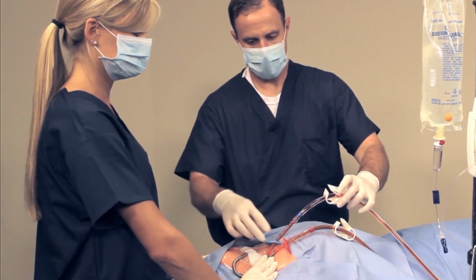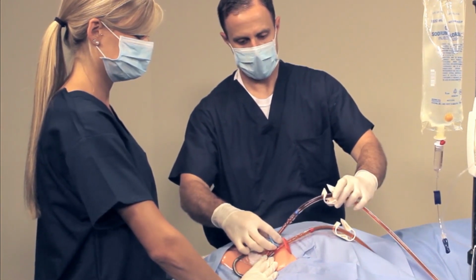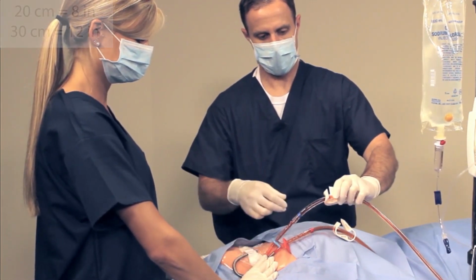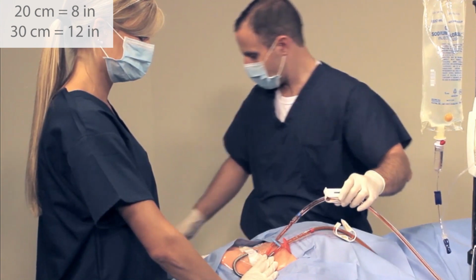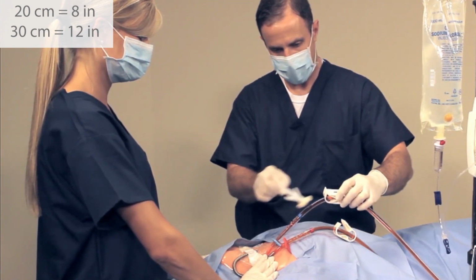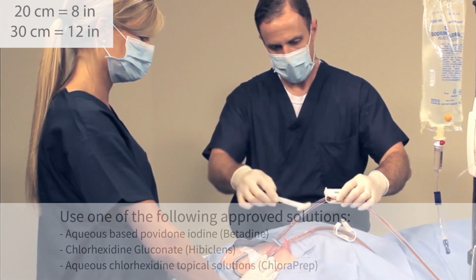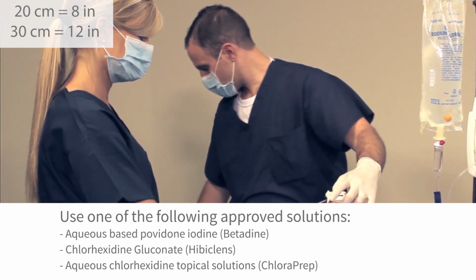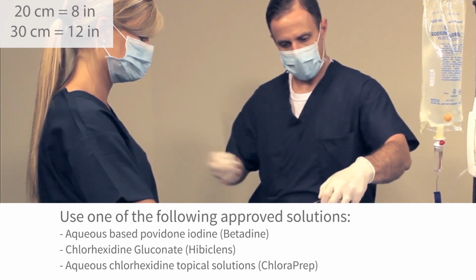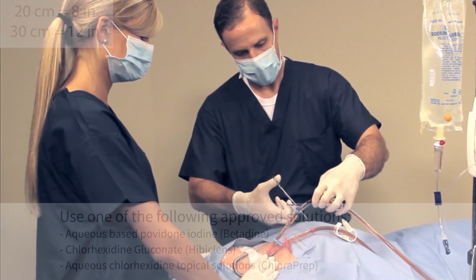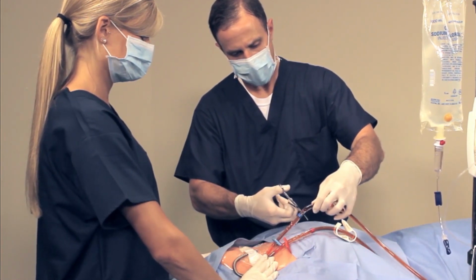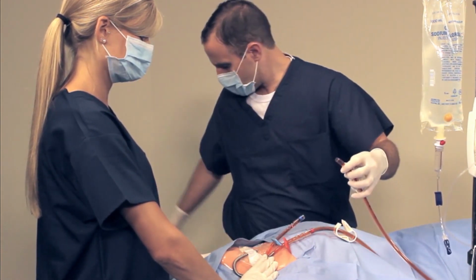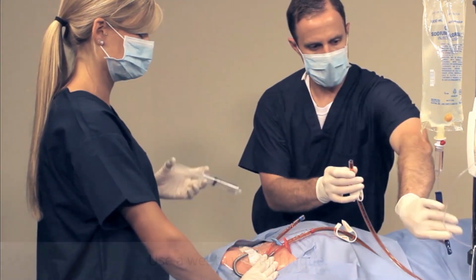Clamp the blue lumen on the catheter. Clamp the blue tube approximately 20 centimeters from the catheter connection. Next, clean and disinfect a 30 centimeter length of the blue blood tubing, starting at the catheter barb connector and moving towards the cartridge. With both clamps closed, cut the blue tube between the clamp and the catheter barb connector in the previously cleaned area.